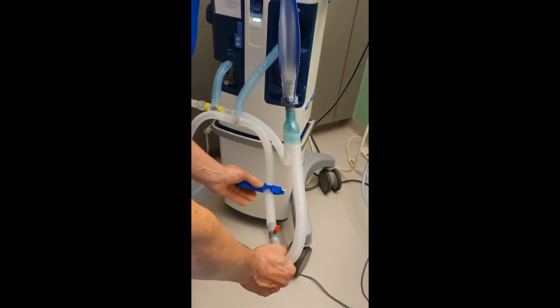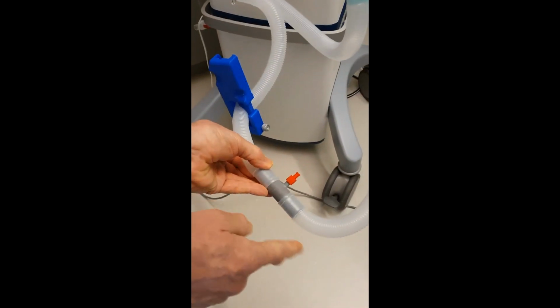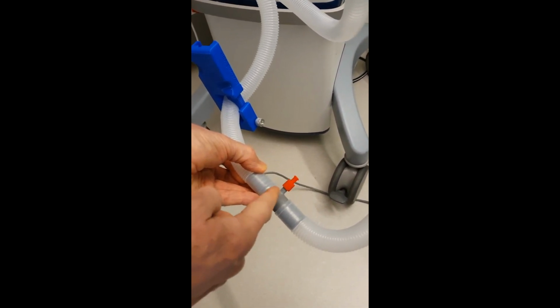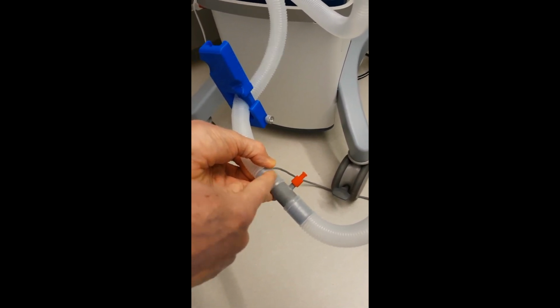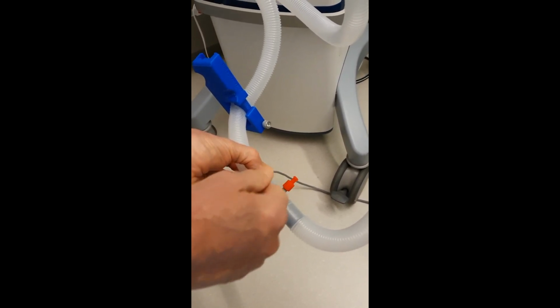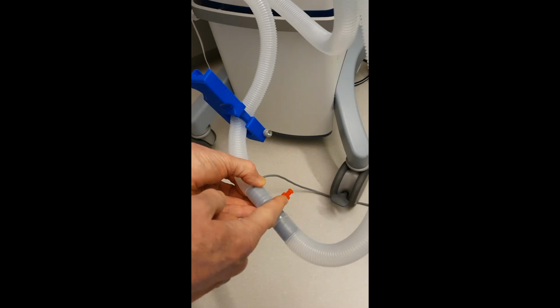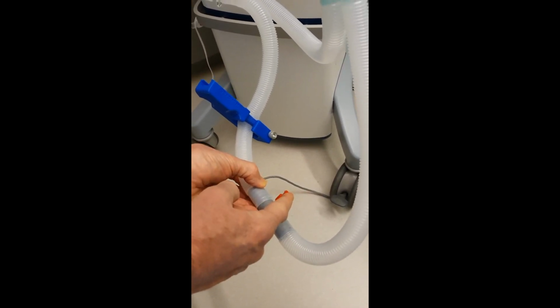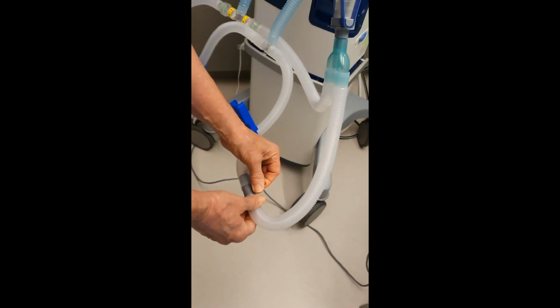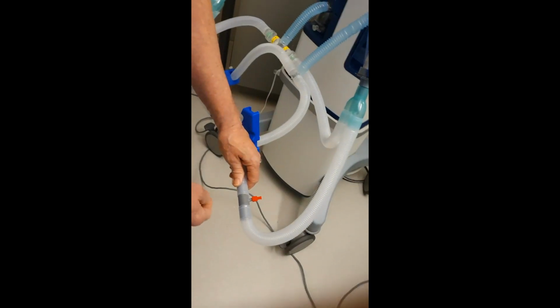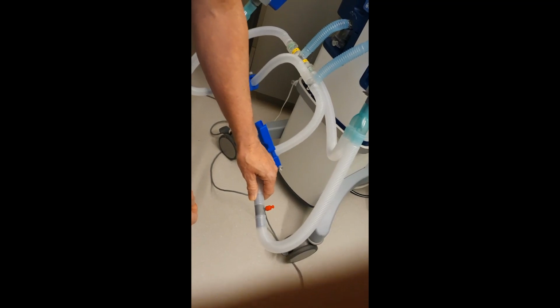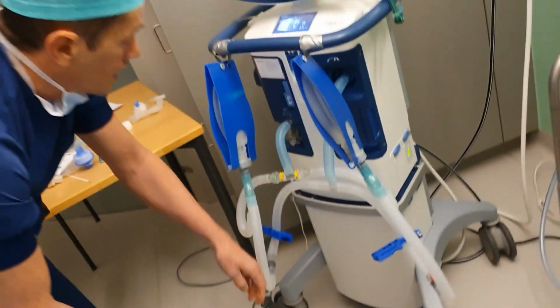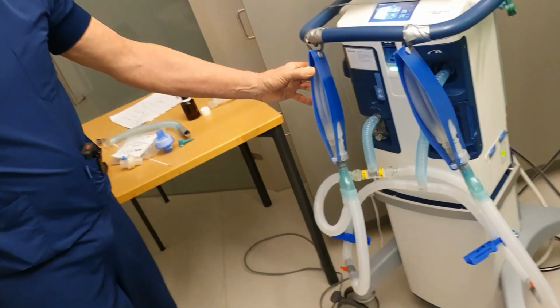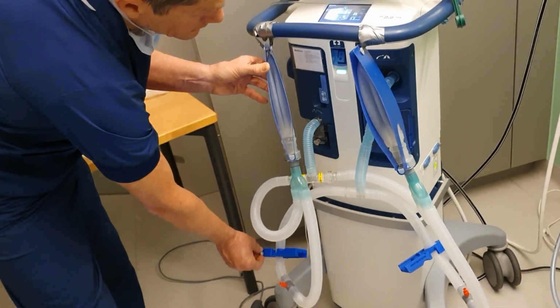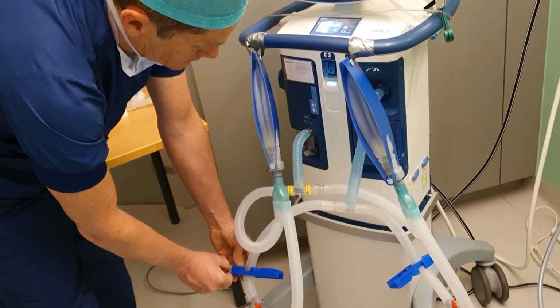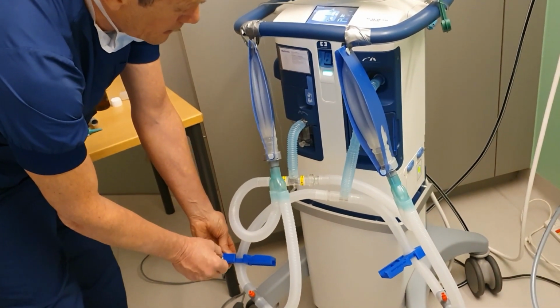In line, we have put the T-piece with the Luer on the side, 22 millimeters inside, to be able to monitor the pressure of the inspiratory limb. It can be put on your scope using a conventional pressure transducer, which is flushed. And in this way, you can compress the tube and adapt.